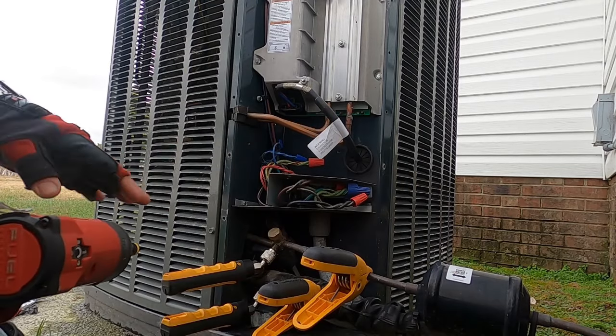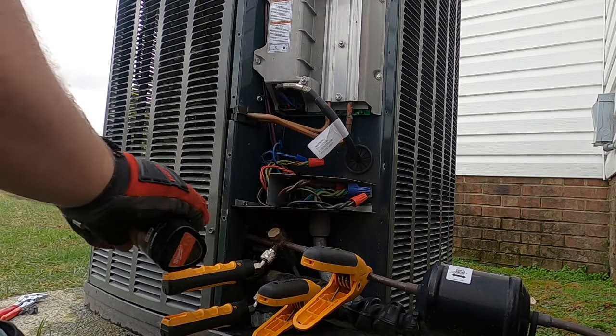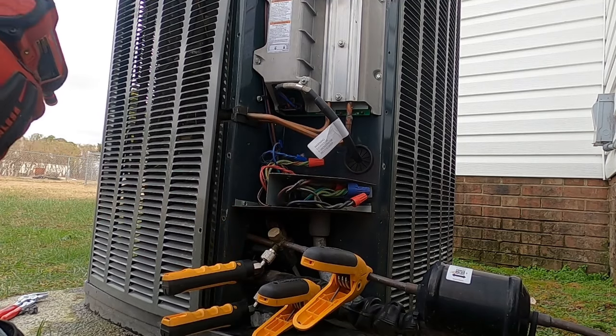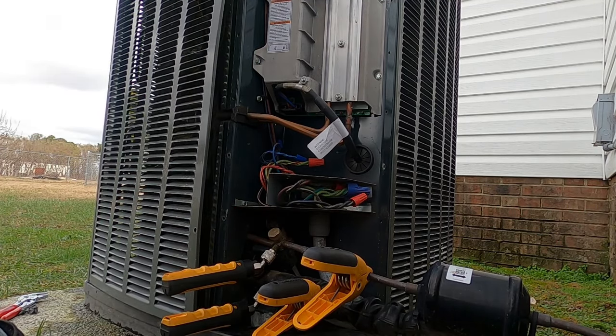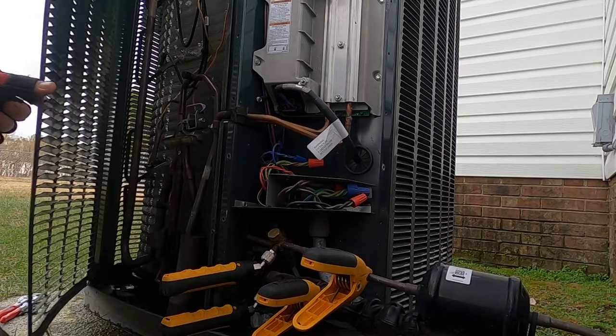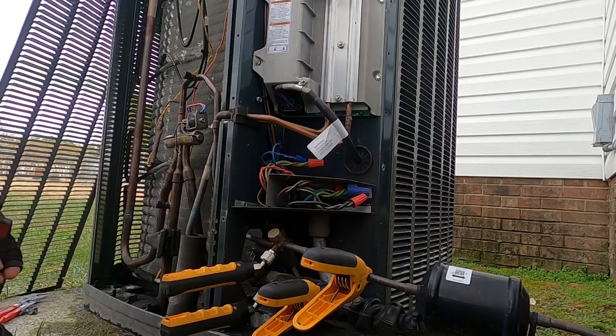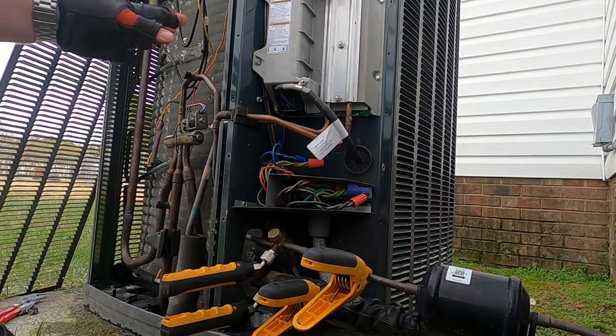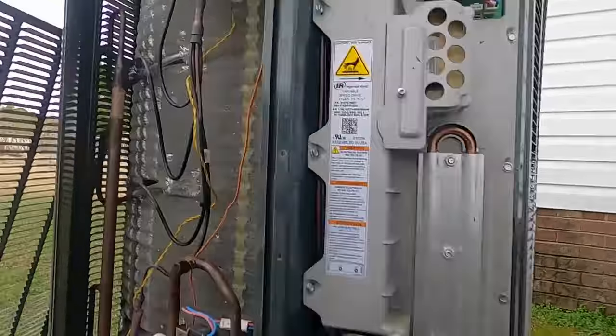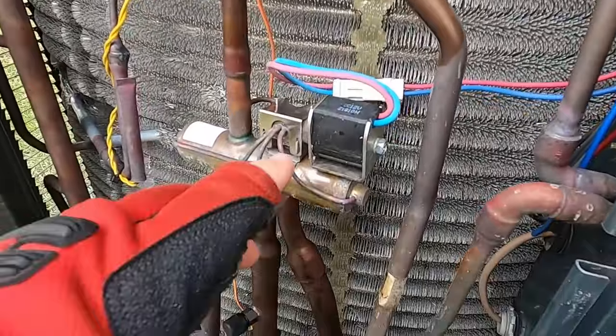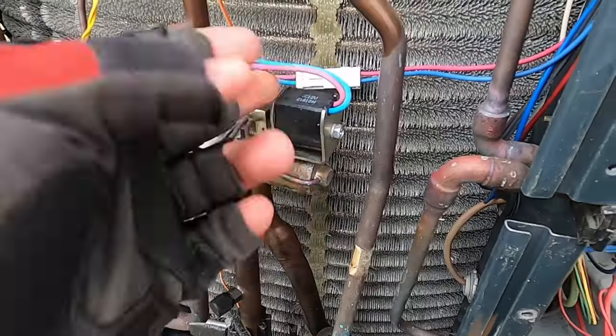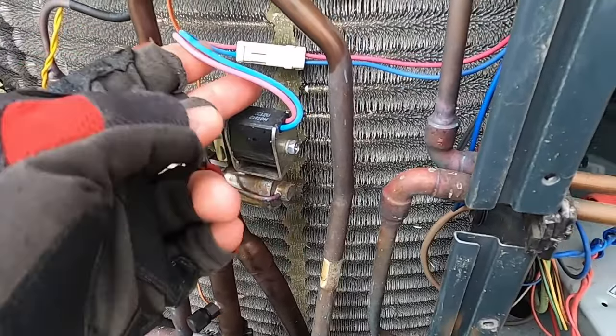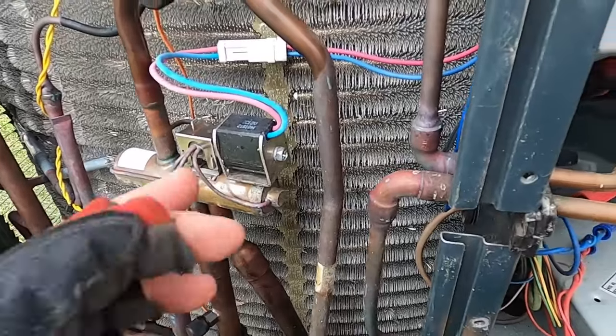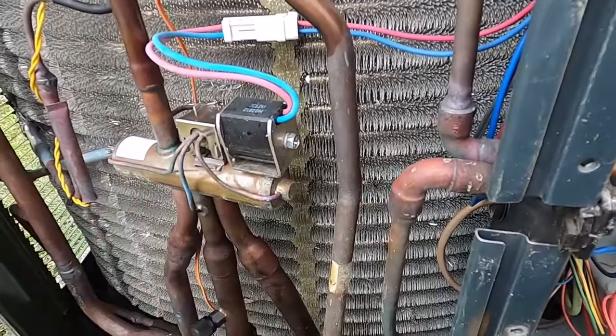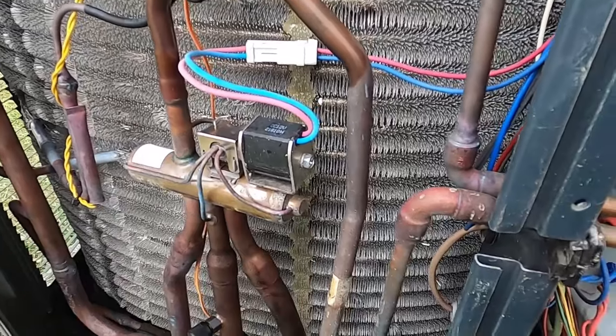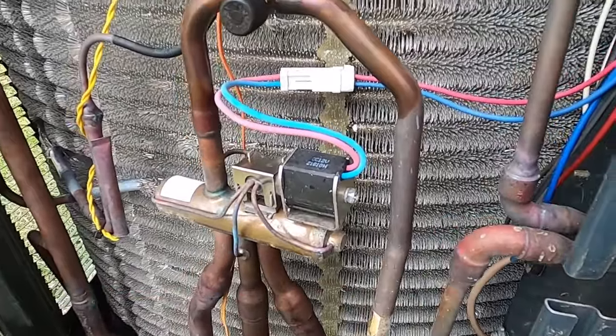But it truly adjusts airflow, and makes awesome dehumidification in a house with one of these. They work great with all the Trane equipment that we've put in for 15 years now. This has really been the least problematic one, but you've got this. It's not a 24 volt solenoid valve. It gets a pulse, one for heating, I think it's 4 volts DC, then it'll get another 11 volt DC pulse to switch back to cooling, or vice versa. It's 11 and 4, but I can't remember which one's heating and which one's cooling.